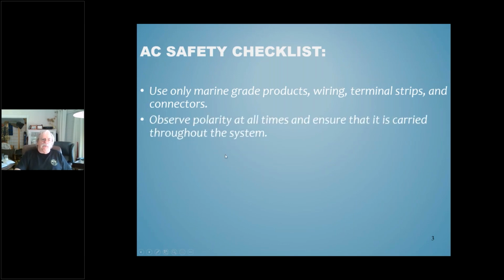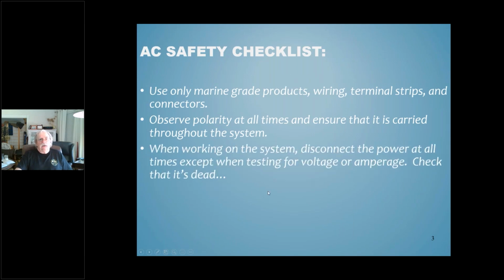It's very important to observe the polarity at all times when you're running wire through the boat and installing equipment. You can have reverse polarity set up at a receptacle and have everything else on the boat be fine. So you need to make sure that you're cautious of where the hots, neutrals, and grounds get connected. Disconnect the power at all times, except when testing for voltage or amperage. Make sure it's totally shut off. You can get tricked. The biggest trick is an inverter that's in sleep mode hidden somewhere.